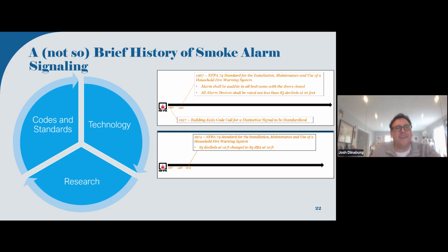So basically in the 20s, we said we really need a distinctive signal and we need to standardize it for fire alarms. So naturally, 40 years later, we came up with NFPA 74 and said it's got to be audible everywhere, and all of the devices need to be rated at 85 decibels at 10 feet. Notice that one there is decibels, not A-rated decibels. If you look at 1974, that became A-rated decibels.